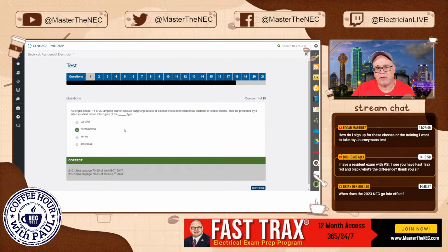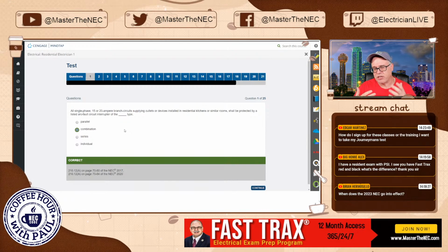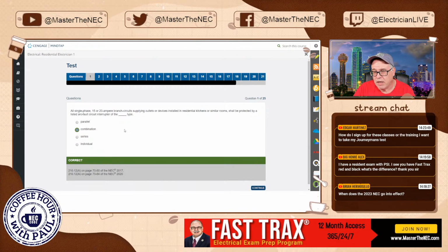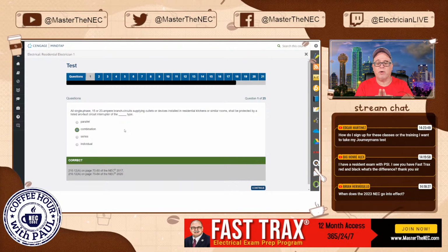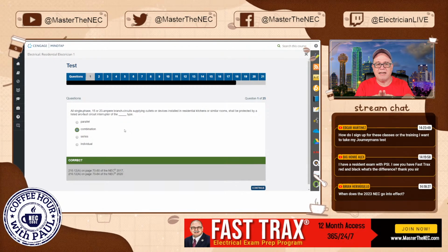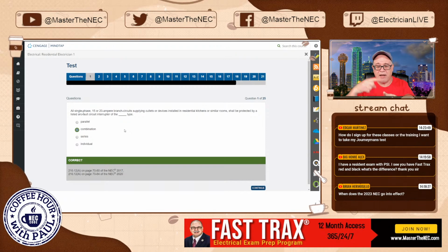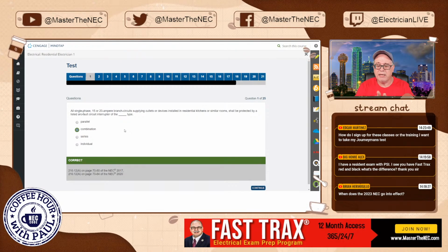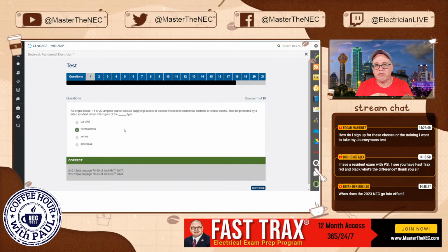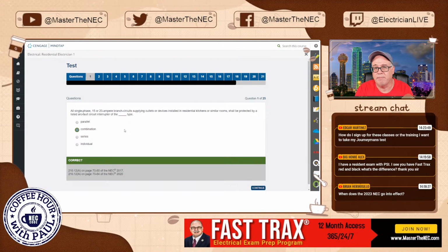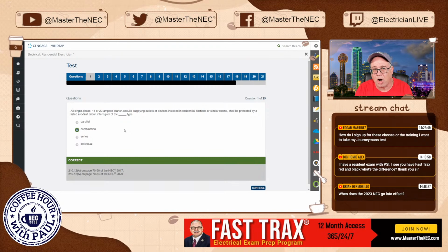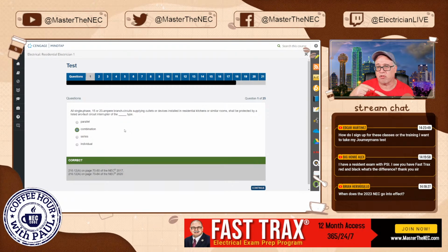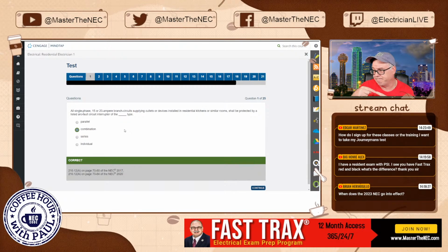One of the other things we teach, and I explain in the program, is the difference between parallel and series. A parallel arc is, for example, where you would have a black and a white next to each other, they get caught and a nail crushes it, then you arc between them. It's not limited by the load. It's an arc that's directly in relation to two conductors that are in parallel, and that is called a parallel arc. A series arc would be a loose termination at a screw where you didn't torque it properly.